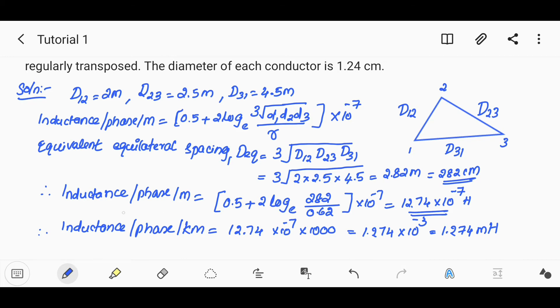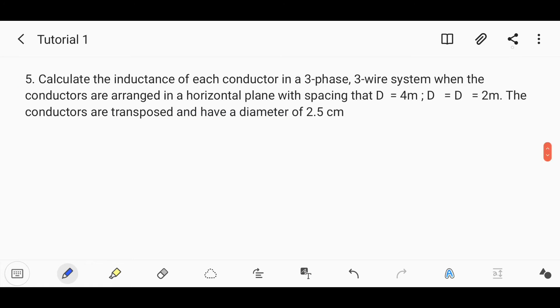The equivalent spacing D_eq comes to 282 cm. With r = 1.24/2 = 0.62 cm, the inductance per phase per meter is 12.74 × 10⁻⁷ henry. The inductance per phase per kilometer is 12.74 × 10⁻⁷ × 1000, therefore it is 1.274 millihenry.